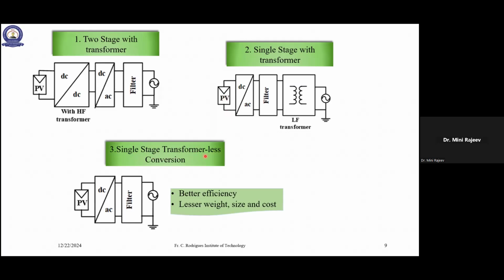Coming to single stage transformerless conversion. Here you can see that there is no transformer at all. There is a PV panel, a DC to AC inverter, and then a filter. The filter is common for all because the inverter output is not a pure AC, so you need a filter in all three cases. There is only one inverter and only one power conversion stage, similar to the previous one. So the efficiency is better than two stage, and the number of components is also lesser, so the reliability is also more.